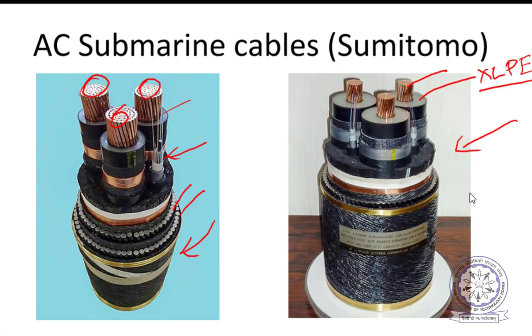And here you can see the structure. This is called metallic armor, and then it is completely sealed hermetically so that no moisture enters into the insulation. In the AC submarine case, it is needed that water should not ingress into the insulation. This is another cable, with a similar structure. Here are the conductors, and after that you can see cross-linked polyethylene insulation, XLPE insulation. Here this is also XLPE insulation. For the AC cable case, the material popularly used is cross-linked polyethylene, which is called XLPE. So these are typical high voltage AC cables.